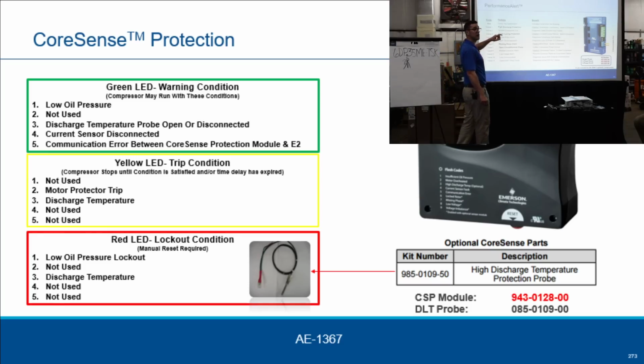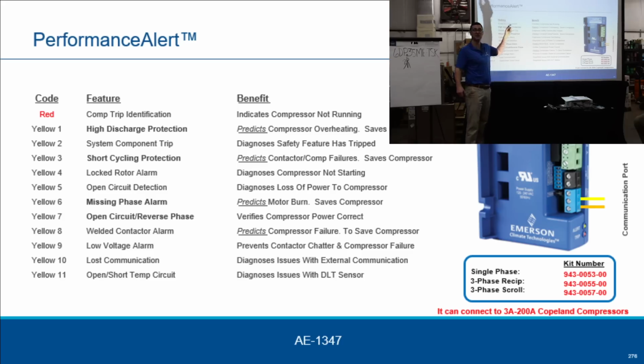Performance alert. You can go to your wholesaler right now and buy these. If you have multiple compressors, 4 or 6D or 3D compressors, or large scrolls, you can buy a device like this that you can put on your compressor to protect your customer's compressor. And we're talking about $2,000, $3,000, $4,000 compressors. One compressor failure could pay for the whole site to have these electronics put on there.